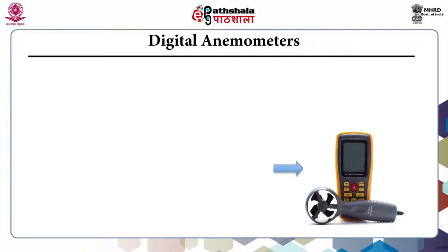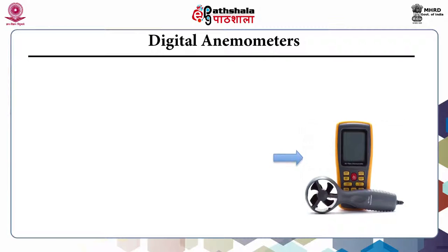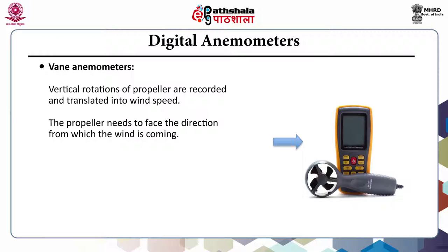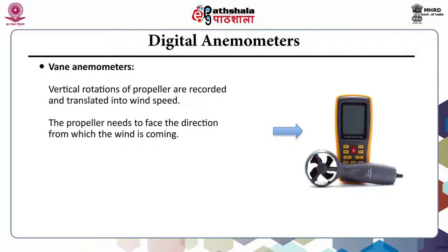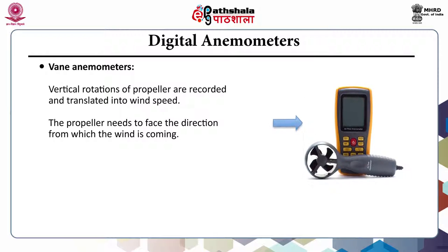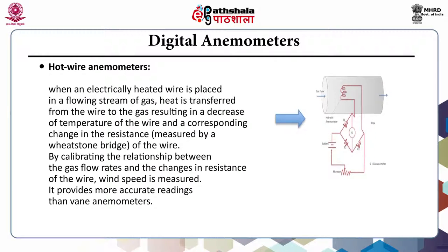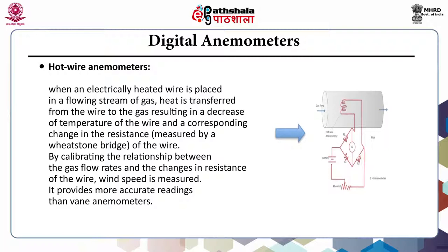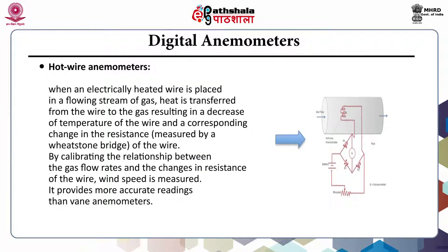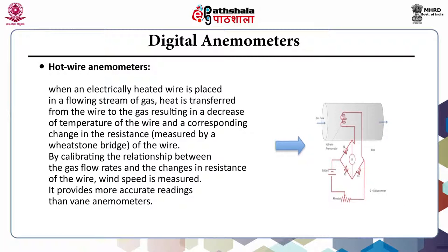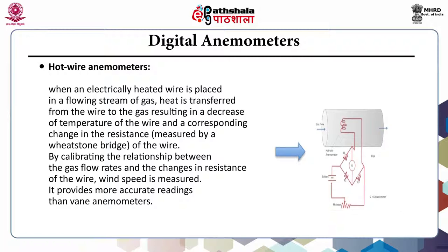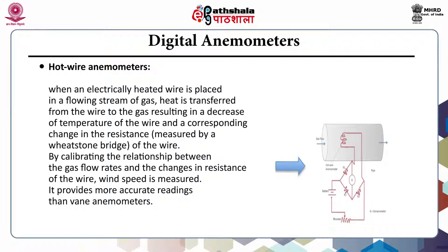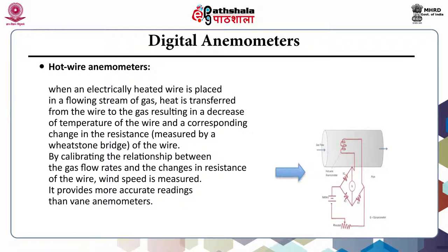Second is digital anemometers. There are two different types: vane anemometers and hot-wire anemometers. In case of vane anemometers, the vertical rotations of a propeller are recorded and translated into wind speed, and the propeller needs to face the direction from which wind is coming. In case of hot-wire anemometers, an electrically heated wire is placed in a flowing stream of gas. Heat is transferred from the wire to the gas, resulting in a decrease in temperature and a corresponding change in resistance. By calibrating the relationship between flow rate and changes in resistance, wind speed is measured. It provides more accurate readings than vane anemometers.